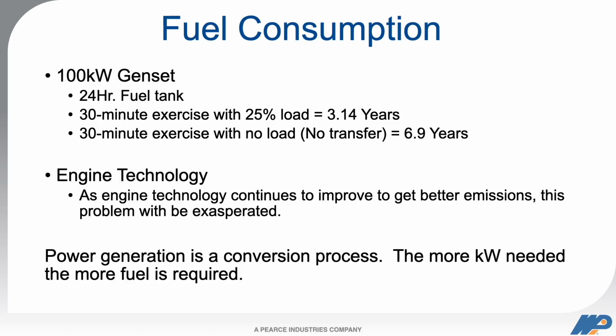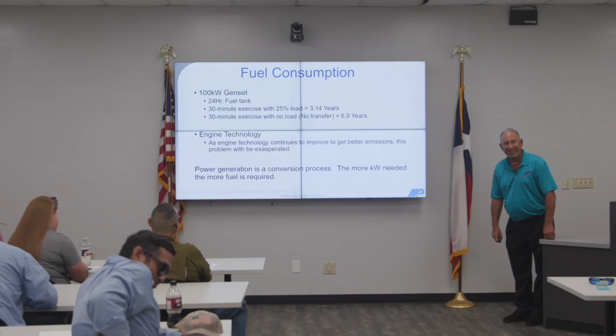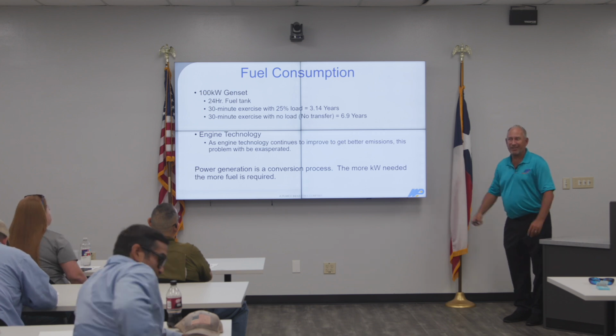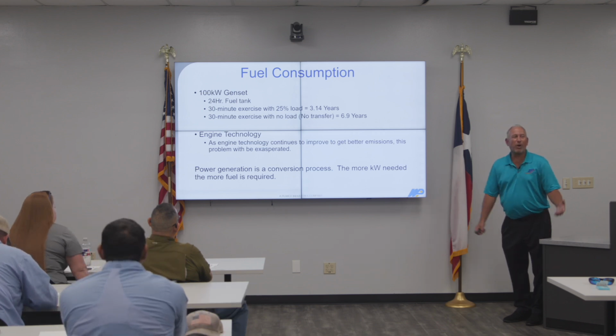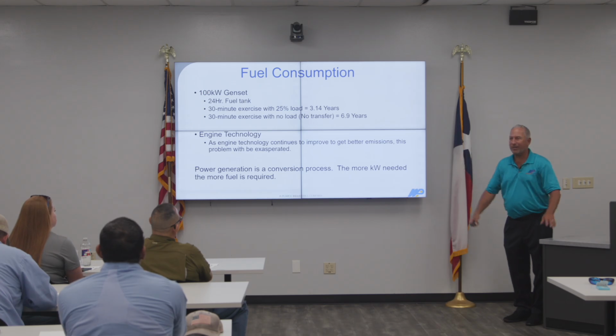This gives you an idea of how long it takes to run through a tank. So you've got a 100 kW diesel, 24-hour tank, 30-minute exercises. If you do no-load transfers, it's almost 7 years to go through that fuel, when they tell you to do something about it in 18 months. They just don't run, they don't run. And when you run it without load, I'm like, what are you doing?